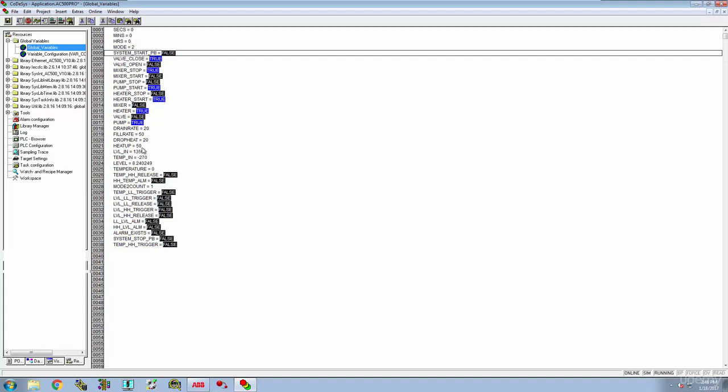Those, I know they've got to be somewhere in the list. Here we go. Our temp in. And our temp in is actually dropping. That's not good. And our temperature is still equal to 0, of course. So we know the logic is not working on our temp in, period. So our level is coming in, and that's working pretty well. And let's see, that's getting up 22, 23.